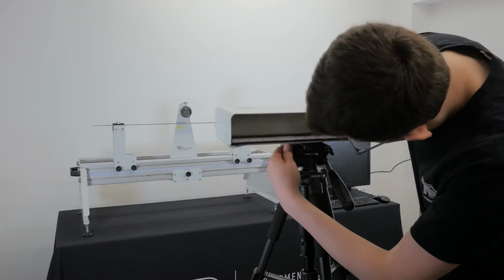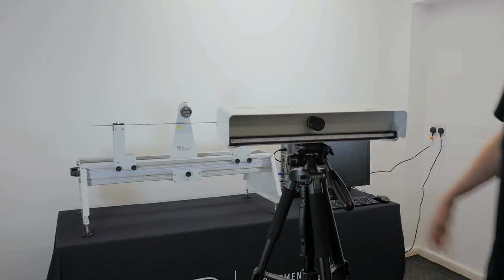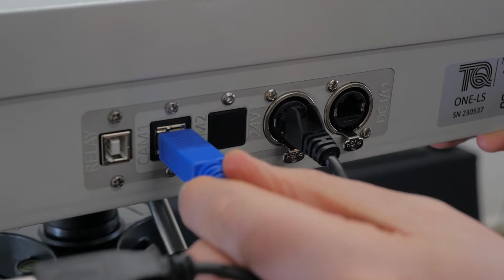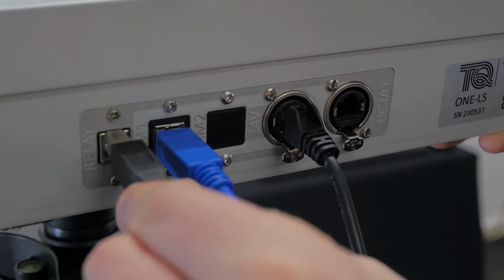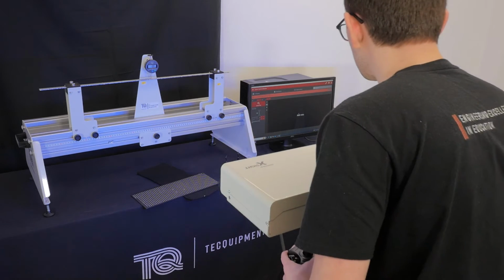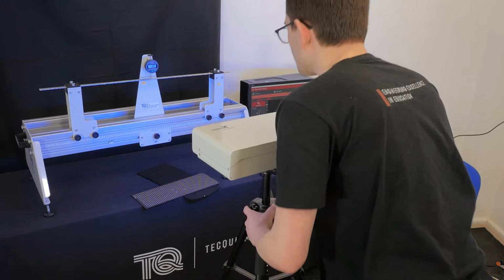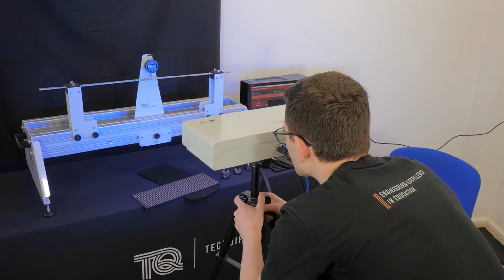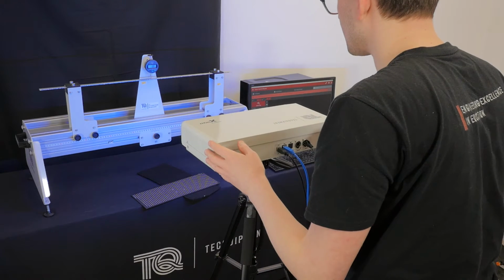To use DefleX, use the 1/4" threaded hole to attach the unit on a tripod, or use the 2 M6 screws for mounting. Plug in all the cables and connect the apparatus to the electrical supply. Set up your desired experiment and place the camera at the desired distance. Further information on optimal distances can be found in the user guide. For the camera to work properly, the system needs to be well focused, and the aperture needs to be set according to the lighting conditions.